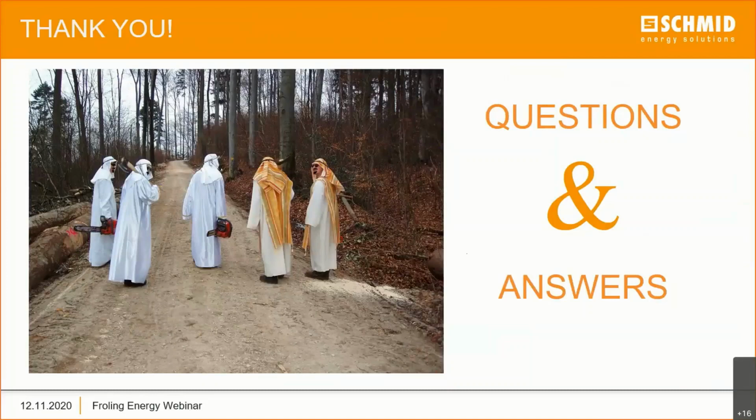So we have succeeded. In fact, we beat the PM 1.0 and the 2.5 emissions criteria, which are the main criteria that we're judged on, with the test on site at these different boilers that are over the 2 million BTU input. Those have been beating the requirement by 50%, and that's utilizing just the standard, either the UTS-K or the UTS-R boilers, using the dry chips. And the one thing about our dry chips is they are screened, so that means there's not a lot of sawdust or other fines within that. And that is one of the biggest differences that we see when we run tests. And we've been able to not only run those tests, but then run some variables within the tests to see what passes and what doesn't and what causes a problem.